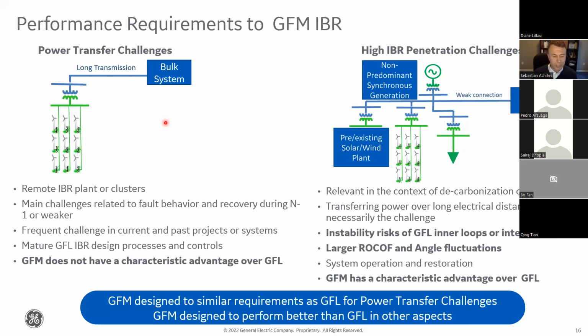And even before you get to that limit, the sensitivity of active power and reactive power to voltage gets really hard to manage. That makes inverter-based resources or a synchronous machine tend to go unstable close to those steady-state limits of the transmission system. So in this type of problem, grid forming technology does not have a characteristic advantage with respect to grid following. It would make sense to try to design grid forming systems to have at least the type of performance that we see in the advanced grid following concepts. But we shouldn't expect to see much more.